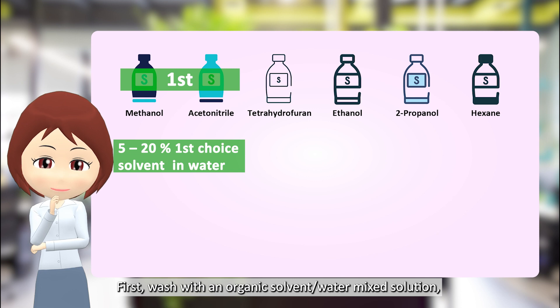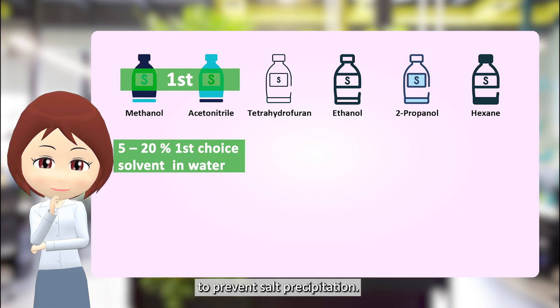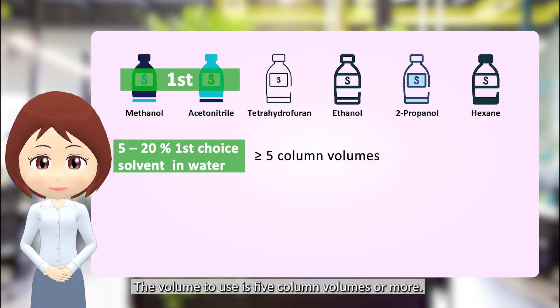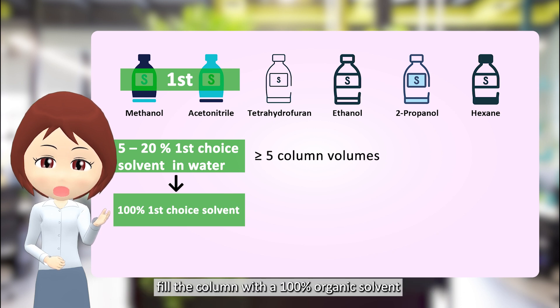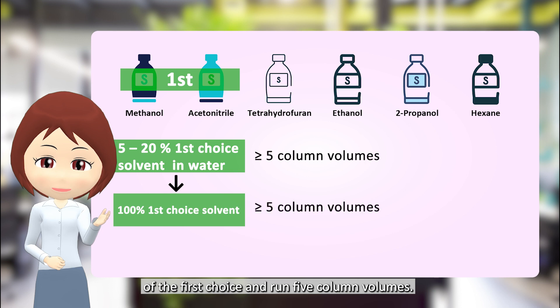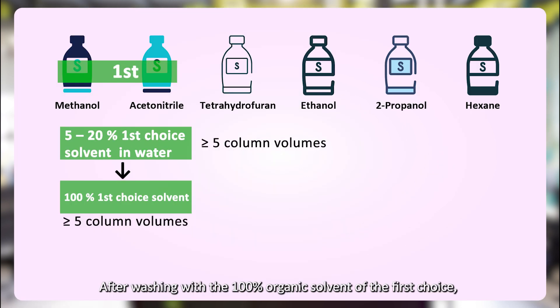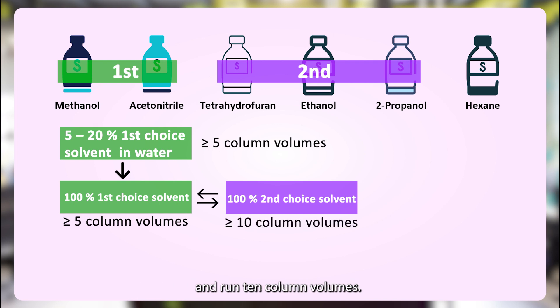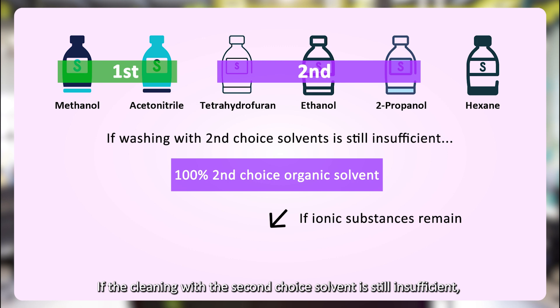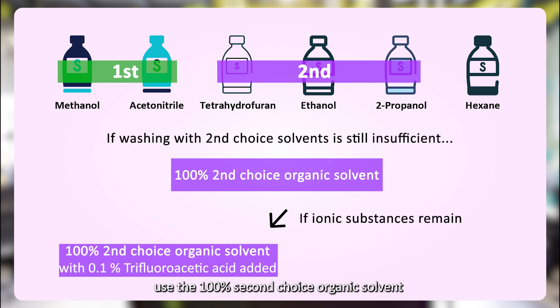For the advanced method, first wash with an organic solvent/water mixture to prevent salt precipitation, using 5 column volumes or more. After that, fill the column with 100% organic solvent of the first choice and run 5 column volumes. Then fill the column with 100% organic solvent of the second choice and run 10 column volumes. If ionic substances remain, use the 100% second choice organic solvent with 0.1% trifluoroacetic acid added to remove them.